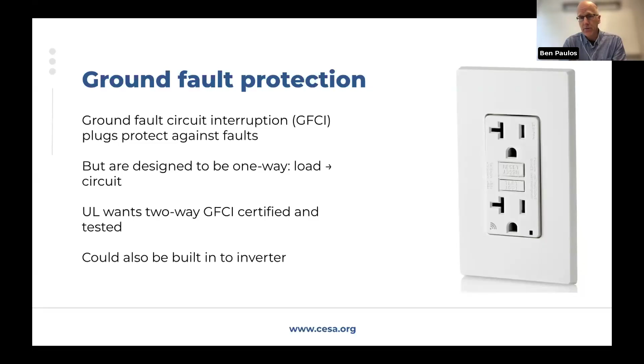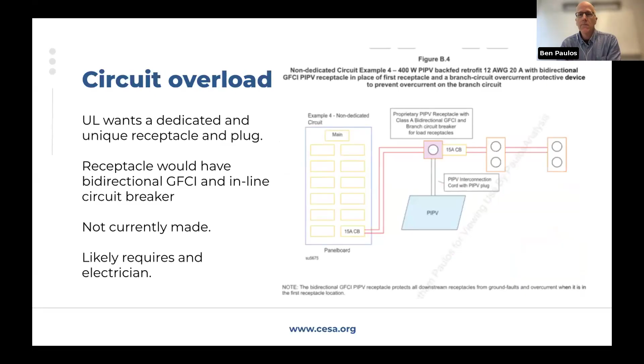This function could also be built into an inverter, so it doesn't have to be a new receptacle. But as I mentioned, UL would like a special receptacle dedicated to plug-in solar. That's really their goal. Possibly marketers will respond to that, and it will be easier for an electrician to install. Or it's possible, since this is a DIY adventure, that people will simply ignore all of this and plug it in wherever they want, which is one of the conclusions I have coming up at the end.